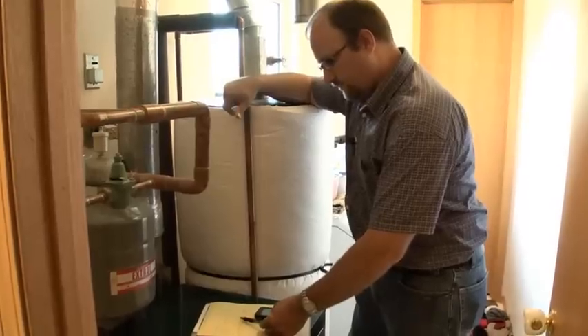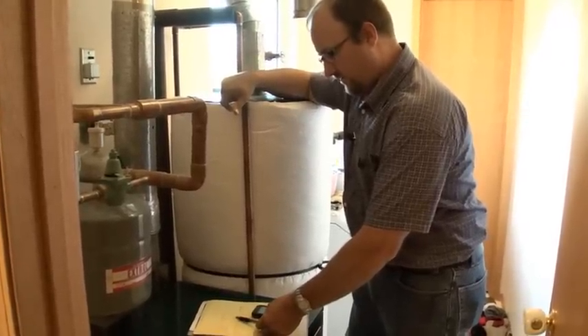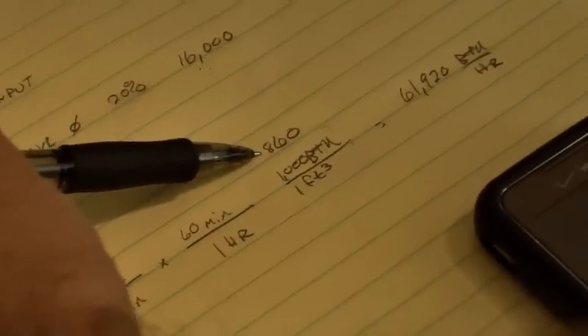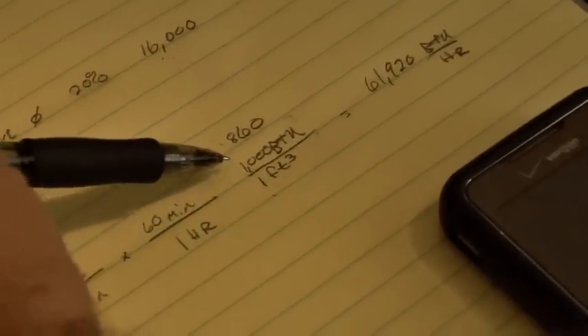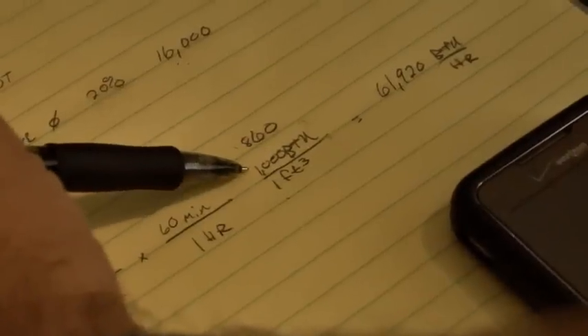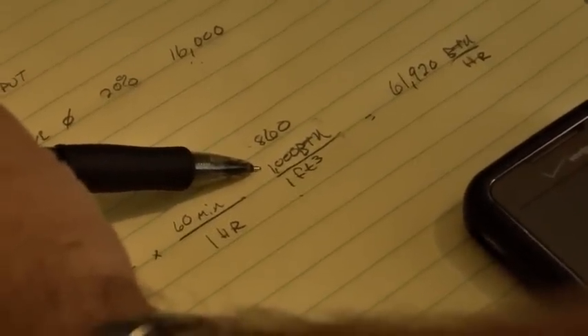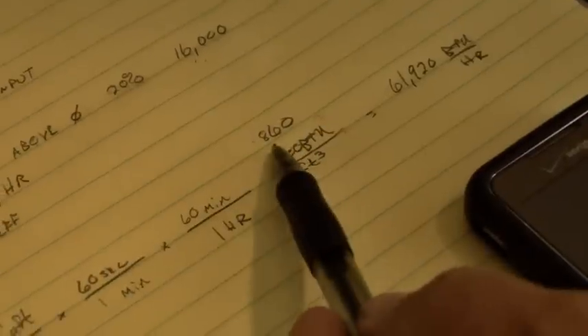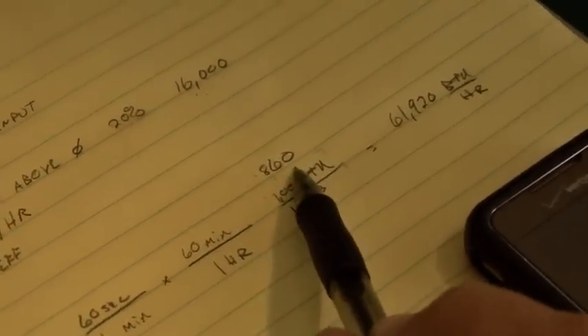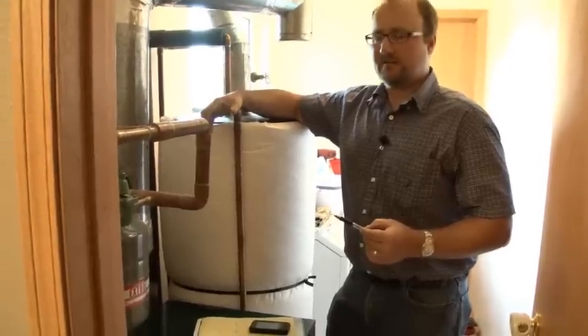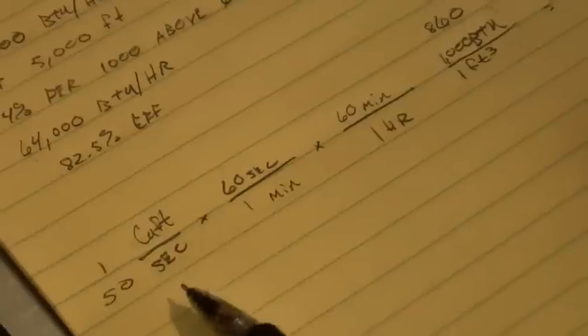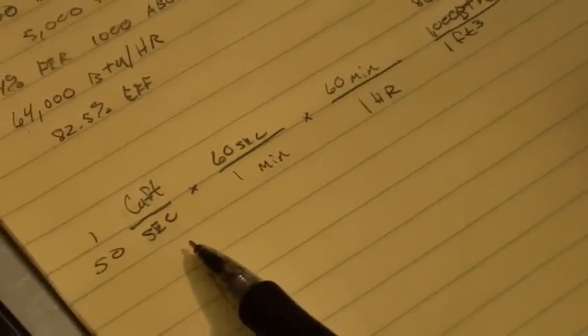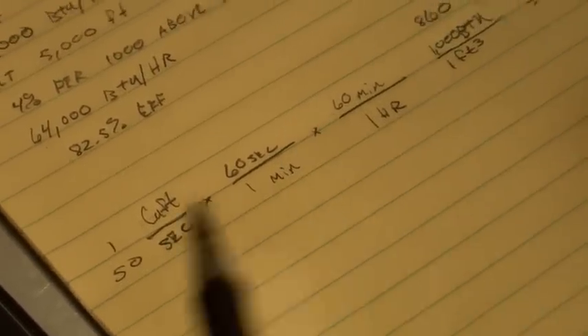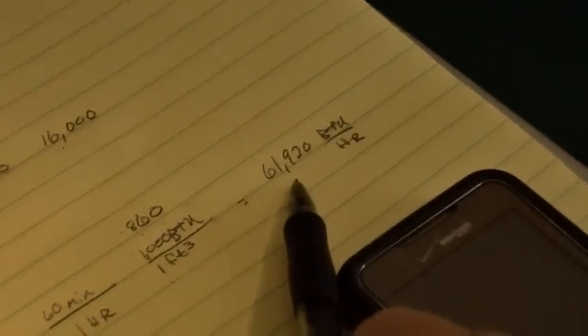In our area, the BTU content of our fuel per cubic foot is about 860 BTUs per cubic foot. As a general rule of thumb, most people use 1,000. In order to get the exact amount, you have to look at the power bill, and there's a little multiplier that tells you how to get it there. And we had 1 cubic foot go through the meter in 50 seconds. That comes out to 61,920. We'll just call it 62,000 BTUs per hour.